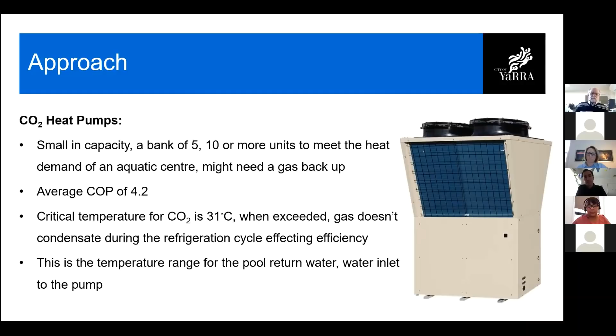So it won't be ideal for pool heating, but that being said, it's usually perfect for domestic hot water applications, because carbon dioxide is more efficient the bigger the temperature difference between the inlet and outlet, and that would be ideal for domestic hot water, where you would need water temperatures of 60 degrees plus. Then we looked at the ammonia heat pumps, and we found that they have industrial scale capacities up to 2,000 kilowatts of heat output, an average COP of 6, so they are extremely efficient, probably one of the most efficient refrigerants out there. They could achieve a combined COP, which is the coefficient of performance, as Alan explained, of 11 if you are using both the cooling and heating sides of the system.